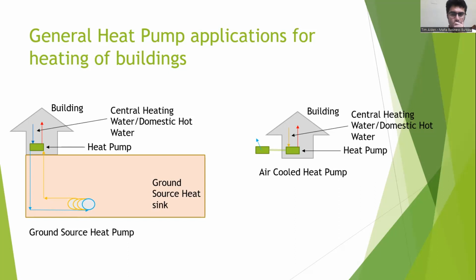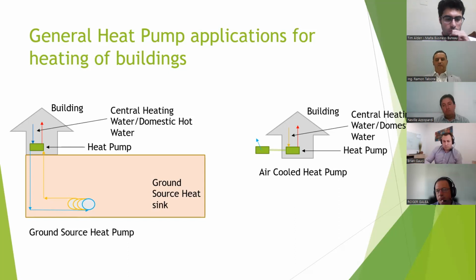Why is this so common in Europe, and why do we dissipate this to the ground? Unfortunately, in Europe, they have sub-zero temperatures. And this is something that's not very comfortable and not something that you want on the condenser side, the outside unit of an air conditioner. So why ground? We all know that the ground tends to keep a constant temperature all year round. Some say that the ground stays at approximately 15 degrees or 12 degrees Celsius in winter and in summer. So this gives you the opportunity of a stable operating mode for your heat pump when you do ground source heat pump.